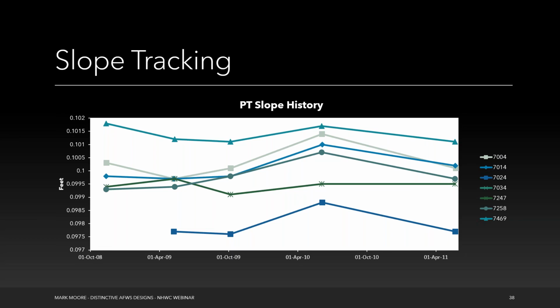So this is a site or a group of sites that was visited every 6 months. And when you're tracking this information, you can track the slopes to see, all right, are my slopes remaining constant over time, or are they drifting up or down? Or, in this case, during one of the site visits, every slope went up. Well, maybe if every slope goes up, it's not something with the PTs, it's something with the calibrator that was used. That's why it's important to track things like PT slope, PT offsets, standard errors.